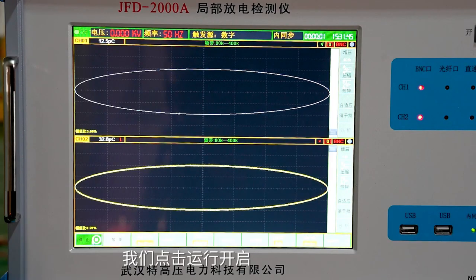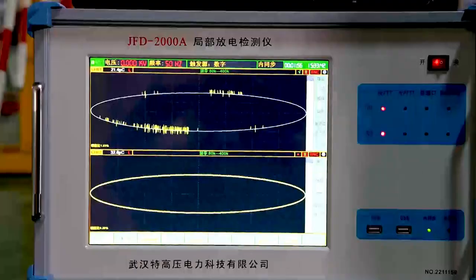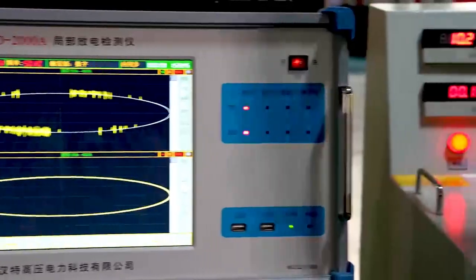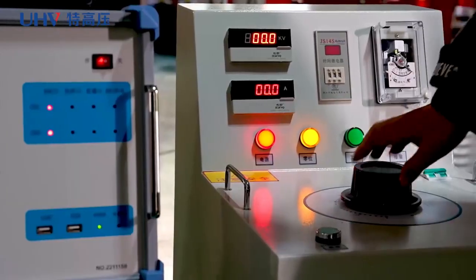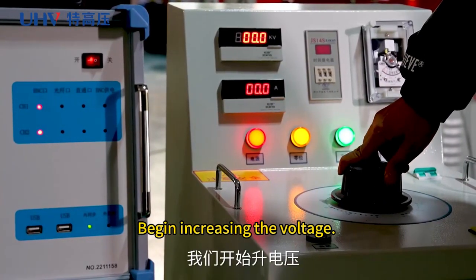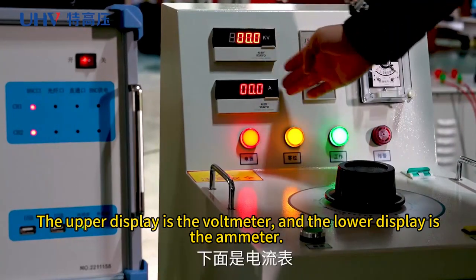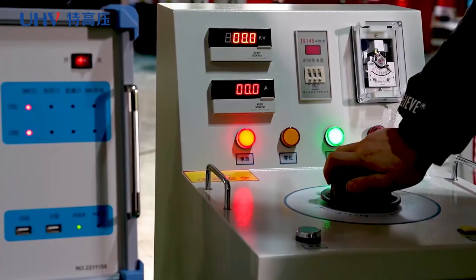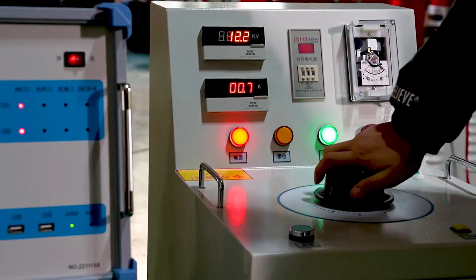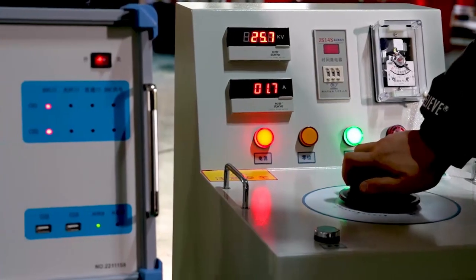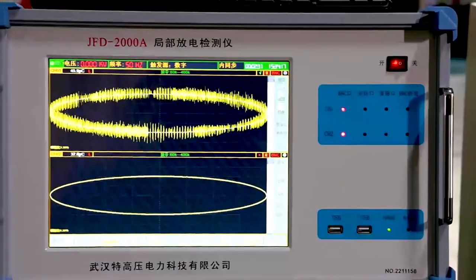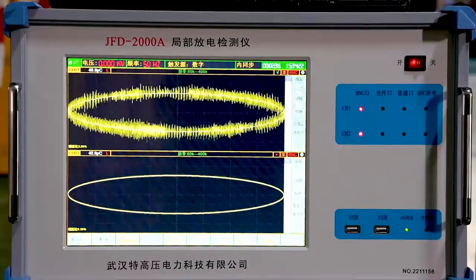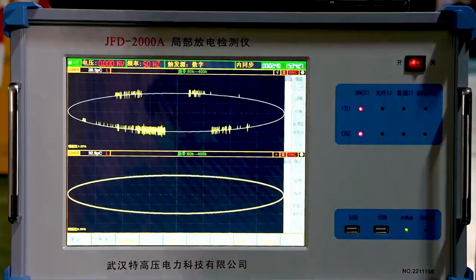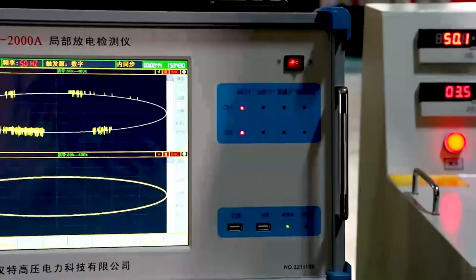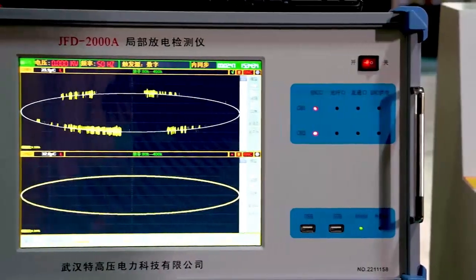Click Run to start. Begin boosting the voltage. Now, power on. Then, reset the voltage regulator to 0. Click Start. Begin increasing the voltage. The upper display is the voltmeter, and the lower display is the ammeter. Here, we only need to increase it to 50 kV. You can clearly see that the discharge level has increased.